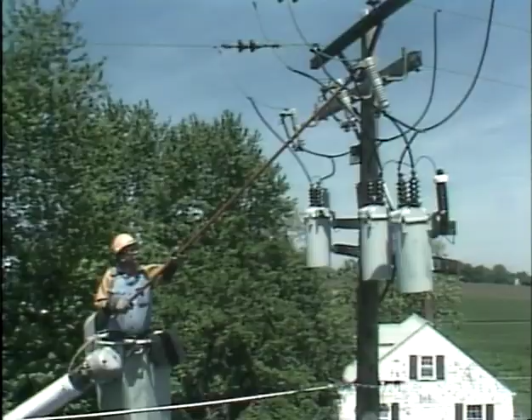When a circuit has been de-energized, the circuit can be isolated by separating the switch contacts. This creates a visible break in the circuit. There is no arc to extinguish because the circuit was previously de-energized. Remember that no-load switches must be operated in sequence. In other words, they should be opened only after a circuit breaker is operated to de-energize the circuit, and closed before the circuit breaker is operated to energize the circuit.